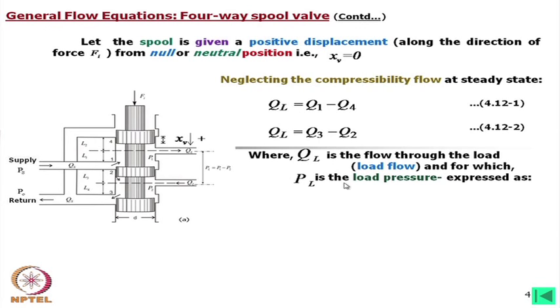The load pressure PL equals P1 minus P2. For a linear actuator, P1 acts on one side of the piston and P2 on the other. For servo valve actuators, the symmetric actuator configuration is normally used, with rod ends at both ends of the piston so that the piston area is the same in both directions. This symmetric arrangement is standard, though exceptions exist.